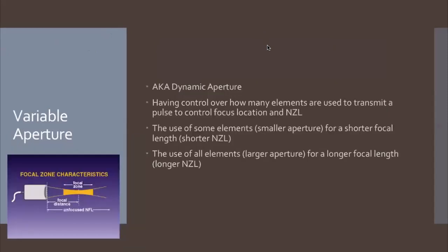All right. So in your book, you guys are going to go all the way to page 58. On 58, we are going to highlight what electronic focus is. Next to electronic focus, I want you to write down the word multi-focus because it means the same thing. And highlight, in addition to steering, phased or phasing can focus the beam as well. An increase in the curve delay pattern, or greater time delays between elements, moves the focus closer to the transducer, whereas a decrease, or shorter delays in the curvature, moves it deeper.